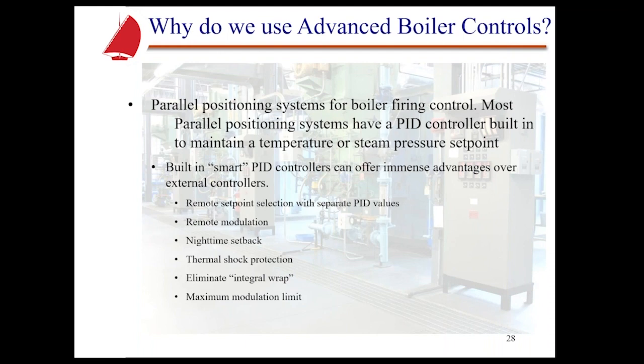You can also incorporate nighttime setback. By having that internal PID controller, you could have that setback and it could sit there at a different set point, if you will, with its own PID parameters and therefore maintain a particular temperature in the boiler when you're not needing it. Thermal shock protection can be built in. When we're starting up a cold boiler, one of the things we want to make sure of is that we don't shock that vessel. So being able to modulate up slowly or not release to modulation until a particular vessel temperature or pressure is realized, that's important too and can be built into the control.